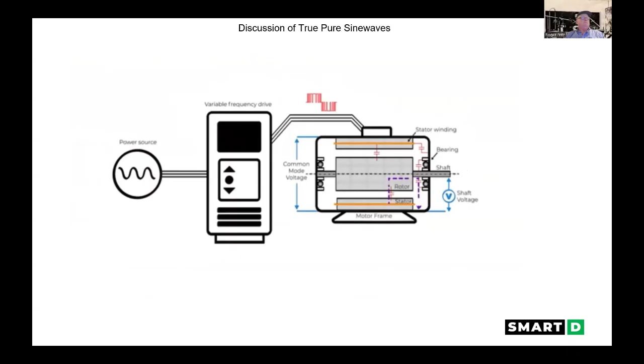The dV/dt of the common mode voltage in the stator windings generates pulse currents flowing to the rotor. Part of this current flows between the inner race and the outer race of the bearings, causing heat in the lubricant. Common mode voltage generates an electric charge stored in the parasitic capacitance between the rotor and the stator. When this charge gets high enough, it breaks the dielectric insulation and is discharged through the insulation of the bearing. The capacitive discharge current can cause fretting of the bearing and raceways and produces temperatures high enough to melt the bearing steel and cause pitting.